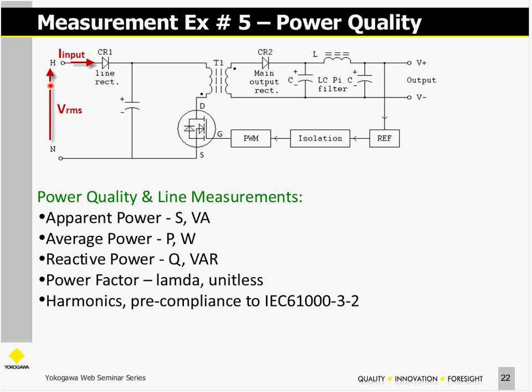As a line measurement here, the voltage and the current will be measured. You can also calculate your average power, much like we just did with the MOSFET; the symbol for that is P, and I use W for watts. Then reactive power, symbol Q, units VAR, volt amp reactive, also power factor, or lambda. These are all line level measurements made here. Typically, you would use an IEC approved AC source.